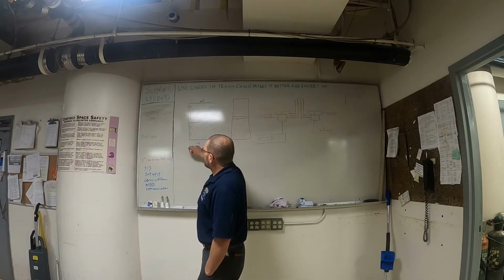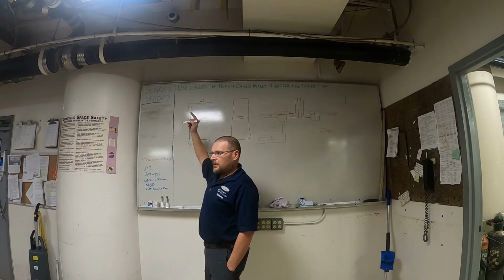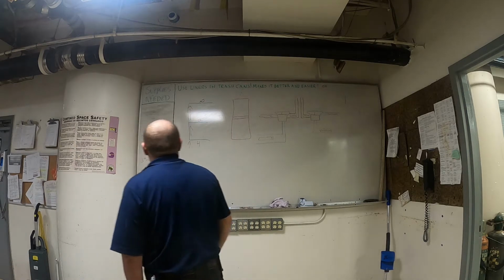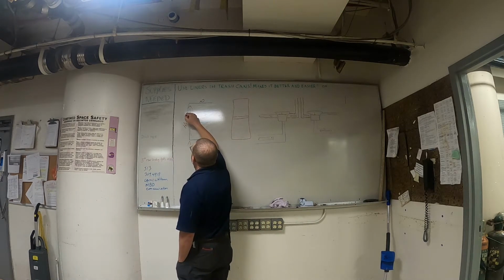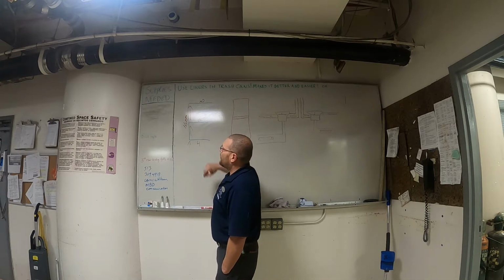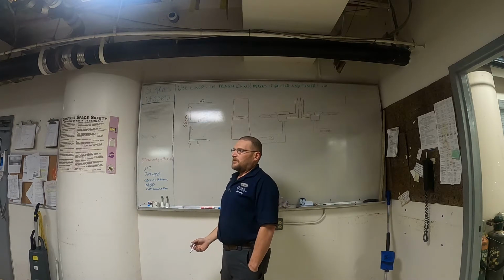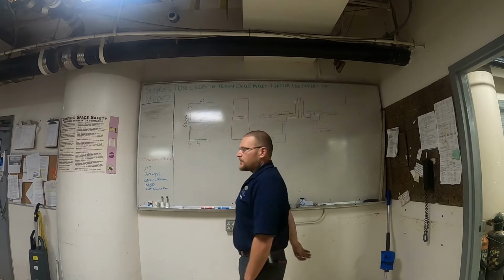Now, this main, where does it travel up at? Housekeeping closet. So if you ever have a leak on 20, 12, or 4, where are you going to shut it down? Housekeeping closet. 4 on 4, under where the housekeeping closet would be.